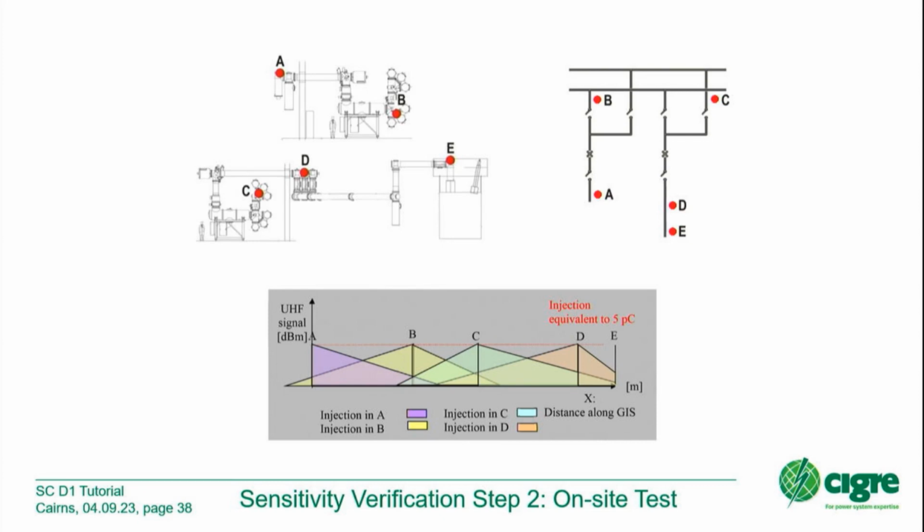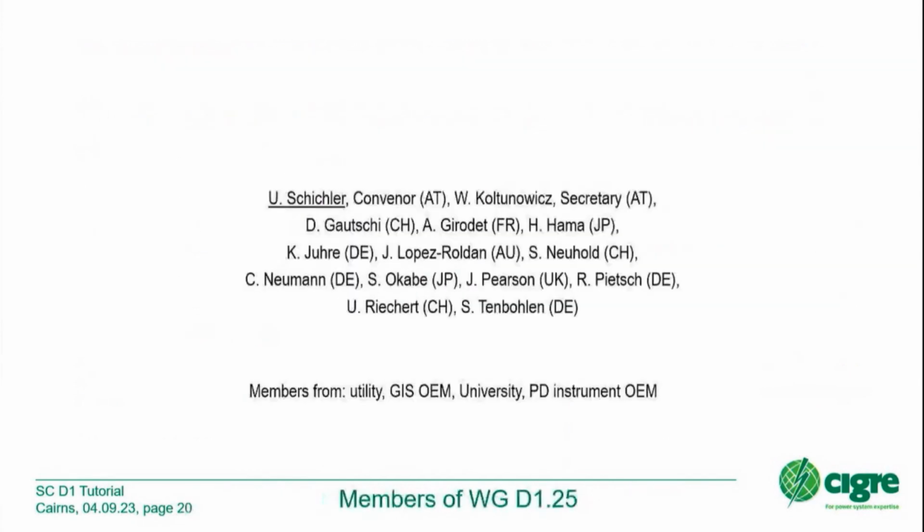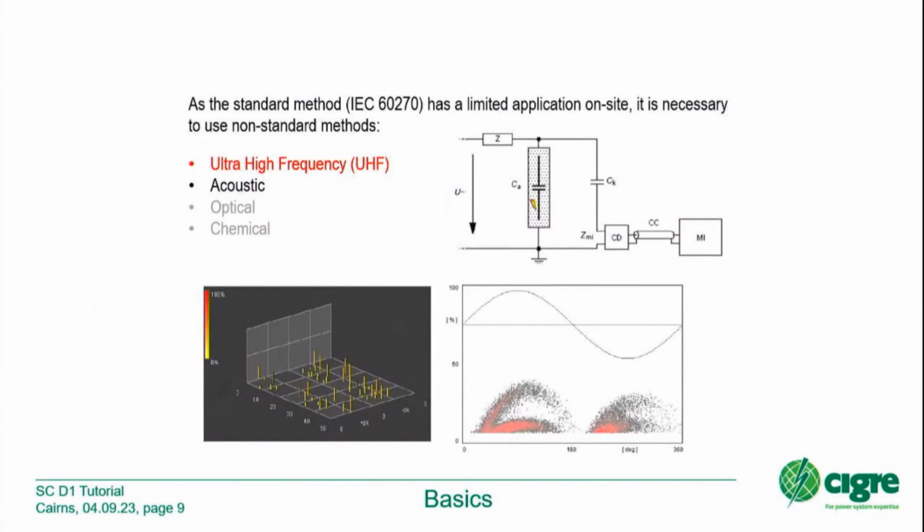Yeah, thank you very much, Uwe, for the nice presentation. I have two questions. The first one, I would like to come back to acoustic and light detection. We have been approached by different companies that were really eager to sell us some products for light and acoustic, but our interpretation in Statnett, the TSO in Norway where I work, is that if you start to have acoustic and light, it's like an old car. When you get the signal for the temperature of the motor, it's too late. Do you have the same interpretation of acoustic and light detection? When you get the signal, it's too late, and consequently, it's not the best solution?